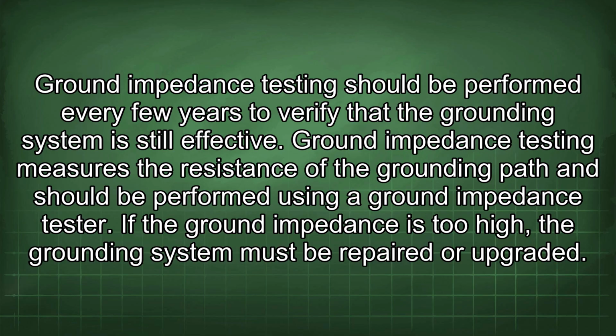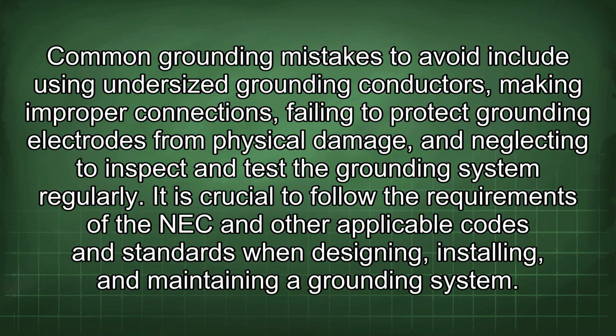Ground impedance testing measures the resistance of the grounding path and should be performed using a ground impedance tester. If the ground impedance is too high, the grounding system must be repaired or upgraded. Common grounding mistakes to avoid include using undersized grounding conductors, making improper connections, failing to protect grounding electrodes from physical damage, and neglecting to inspect and test the grounding system regularly.